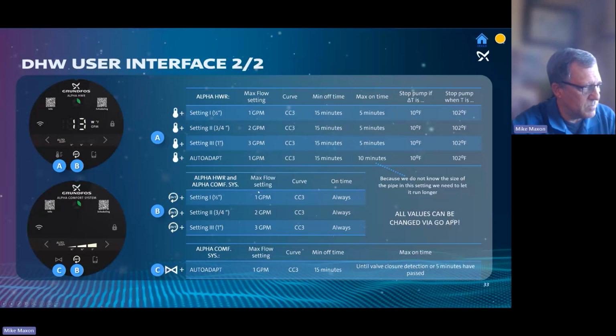Those flow rates go for the 24/7 mode. In 24/7 mode, there's nothing going to turn the pump off. It's just going to always run at that speed. What I've said is, if somebody's putting it in this mode, they should be using an exterior control system, such as maybe a timer, a remote timer. Maybe they want to use a Wi-Fi timer, so they'll put it in this mode instead.